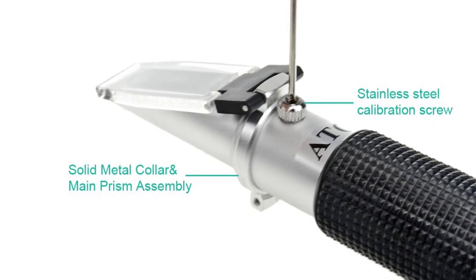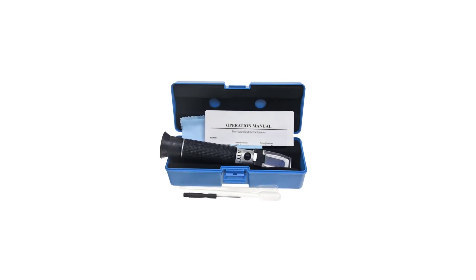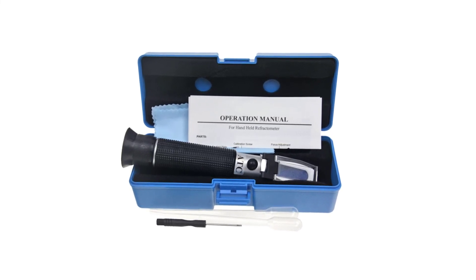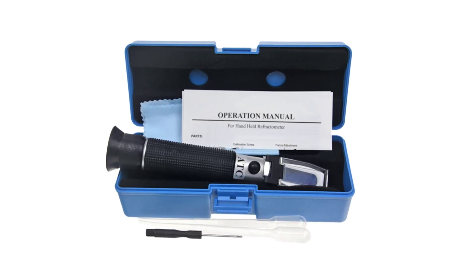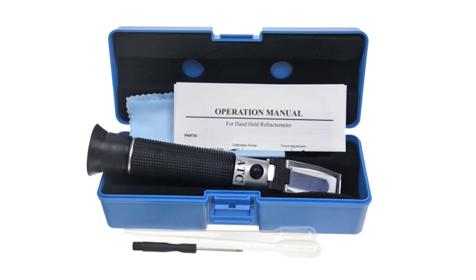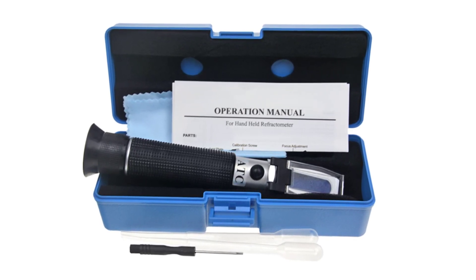Overall, this is a wonderful product from a wonderful company. This meter also comes with a carrying case. Calibration should always be done with RO water — reverse osmosis. Thanks for watching this video. Hope you liked this unbiased review, and please don't forget to subscribe to get news of upcoming reviews. Stay tuned.